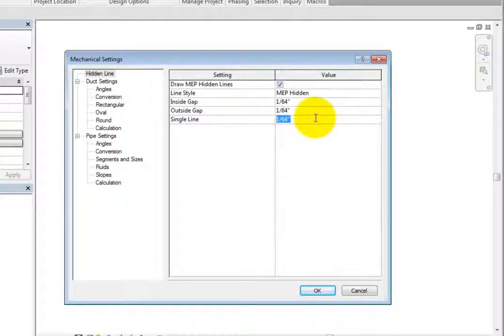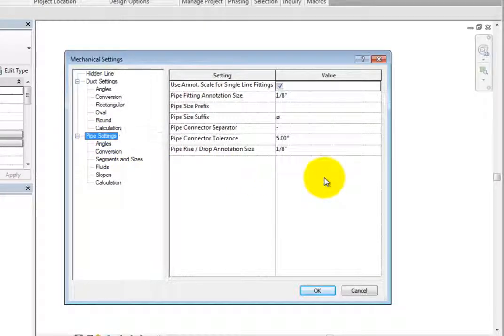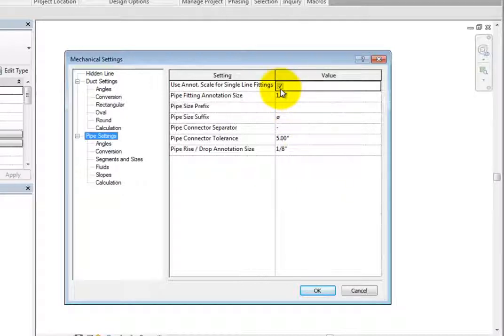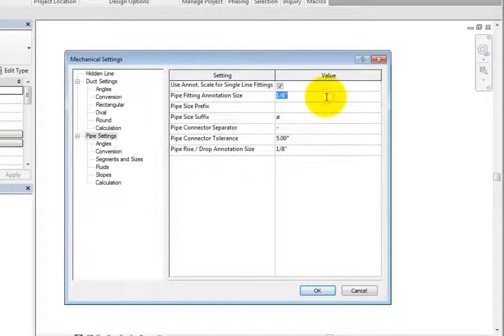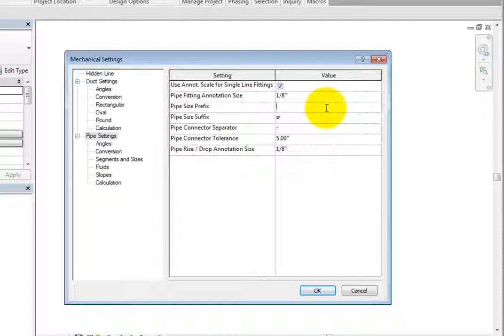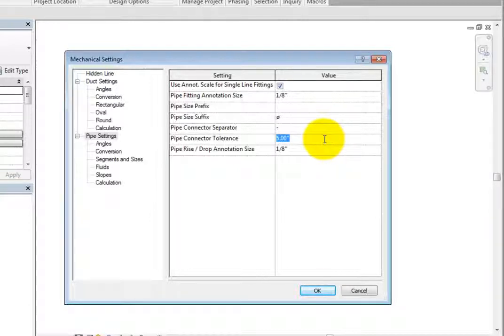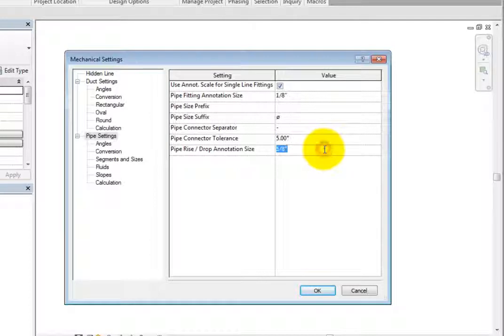Next, click pipe settings to switch to those options. Here, you can choose whether or not to use the annotation scale for single line fittings and then specify the pipe fitting annotation size. The pipe fitting annotation size controls the plotted size of fittings and accessories drawn in single line views. It is also maintained regardless of the drawing scale. Next, you can specify a symbol for the pipe size prefix, pipe size suffix, and pipe connector separator. Then you can enter a pipe connector tolerance and pipe rise drop annotation size.